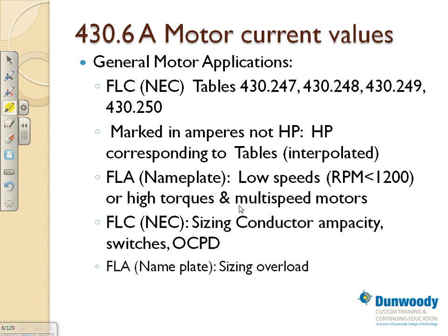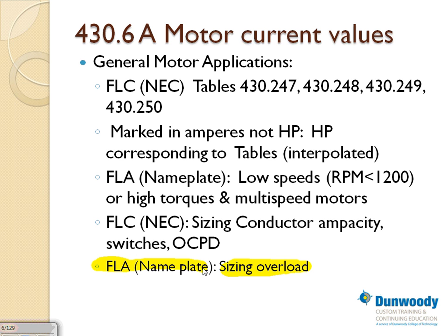Who cares about all this? Because of the full load amp, per code, we can size conductors, we can size switches, disconnect switches, and we size the overcurrent protection device. The full load amp that comes with a nameplate, the only place we use it, guys, is what we call the overload. The overload is sized from the nameplate full load current. So every motor that you can buy is going to have two full load amps. One coming from the NEC code book and one printed on the nameplate of that motor. The one from the NEC code book, you can size everything. The only thing you use the nameplate full load amp for is to size the overload.